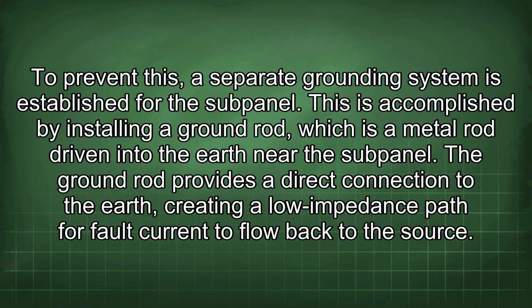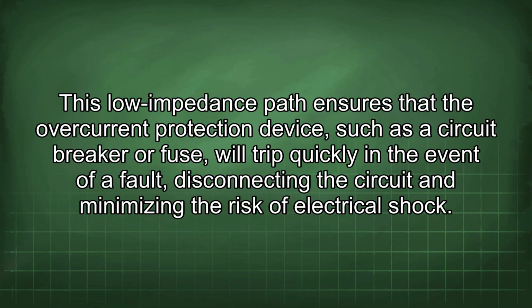To prevent this, a separate grounding system is established for the subpanel. This is accomplished by installing a ground rod, which is a metal rod driven into the earth near the subpanel. The ground rod provides a direct connection to the earth, creating a low impedance path for fault current to flow back to the source. This low impedance path ensures that the overcurrent protection device, such as a circuit breaker or fuse, will trip quickly in the event of a fault, disconnecting the circuit and minimizing the risk of electrical shock.